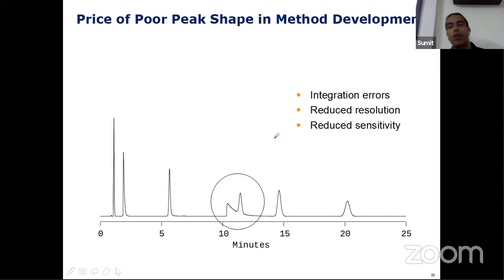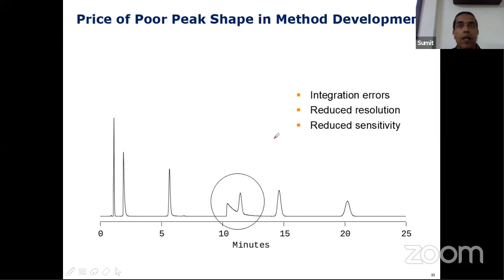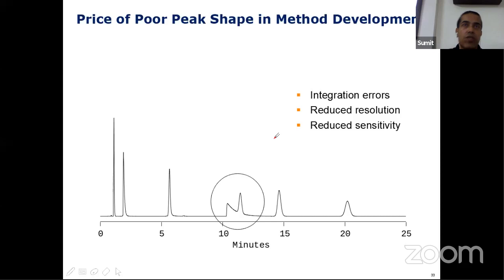I have been talking about poor peak shape all the time. What's so wrong with poor peak shape — does it really matter when you talk about method development? Yes, it does. A poor peak shape can give rise to integration errors. Integration is very important when talking about quantification of your peak, because if your integration goes wrong, your quantitation goes wrong as well. Poor peak shape can give rise to reduced resolution because the peaks are not well separated. At the same time, a poor peak shape can also give rise to reduced sensitivity — just like a Gaussian peak like a triangle: if the triangle height goes down, obviously the width goes up, and that's why it reduces sensitivity.